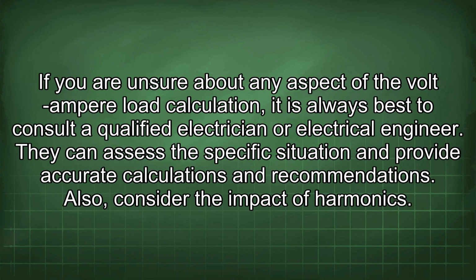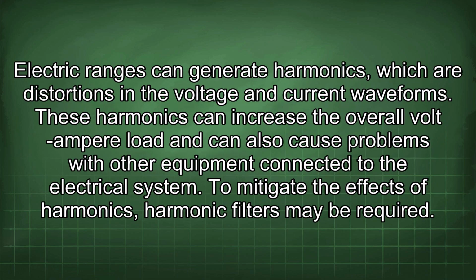If you are unsure about any aspect of the volt-ampere load calculation, it is always best to consult a qualified electrician or electrical engineer. They can assess the specific situation and provide accurate calculations and recommendations. Also, consider the impact of harmonics. The electric ranges can generate harmonics, which are distortions in the voltage and current waveforms. These harmonics can increase the overall volt-ampere load and can also cause problems with other equipment connected to the electrical system. To mitigate the effects of harmonics, harmonic filters may be required.